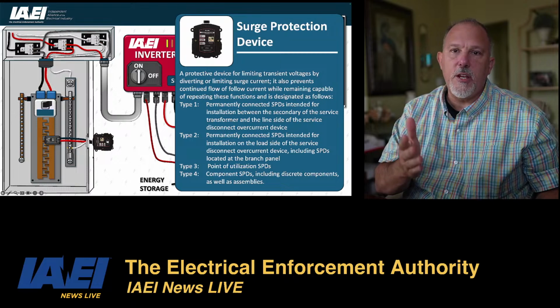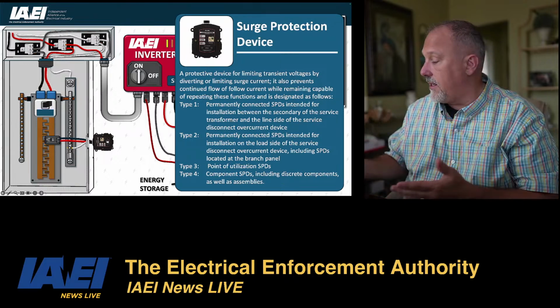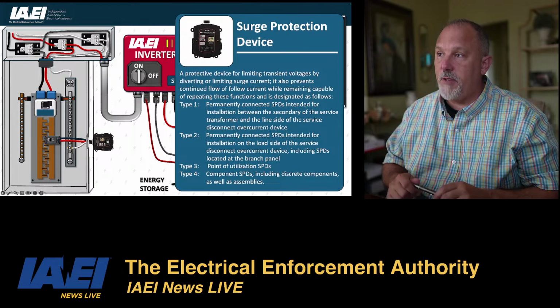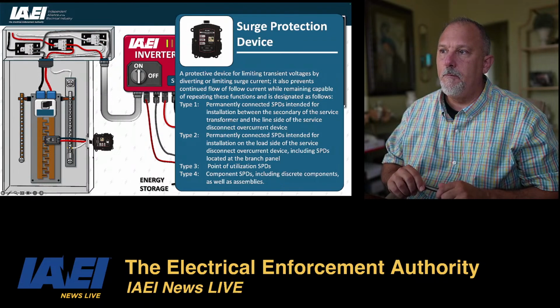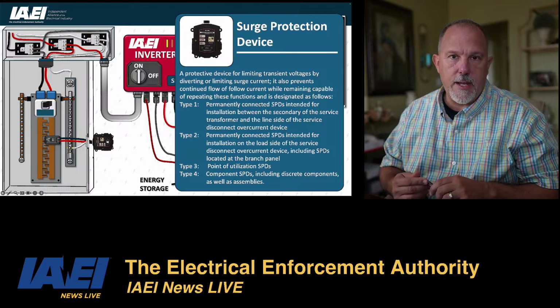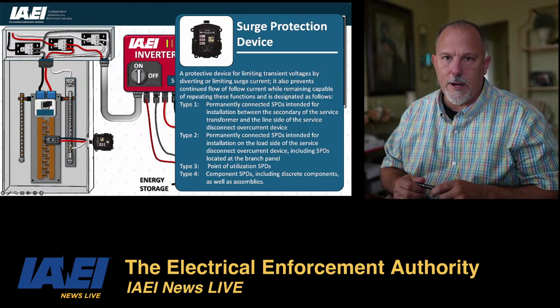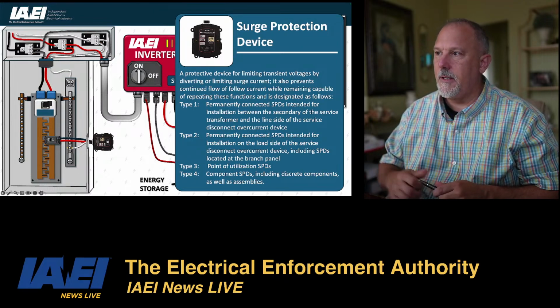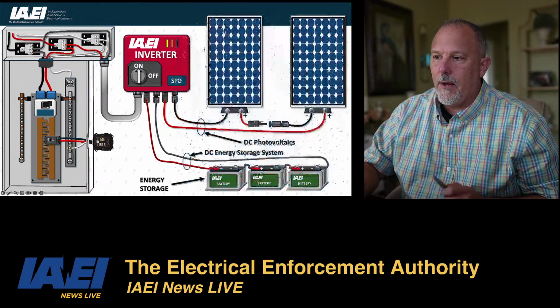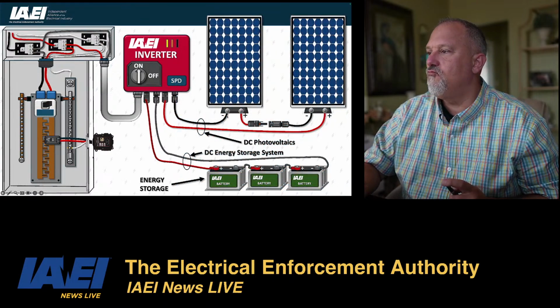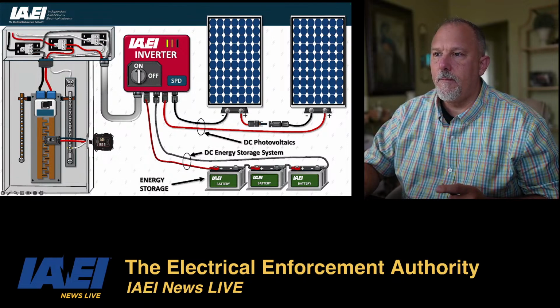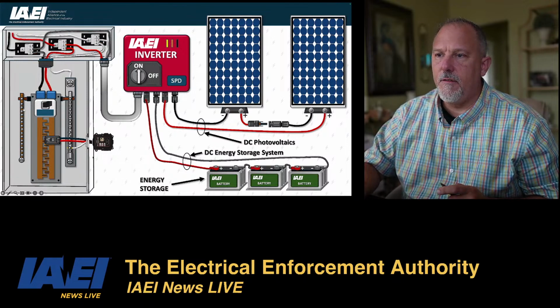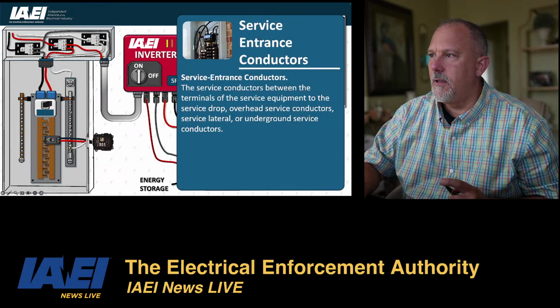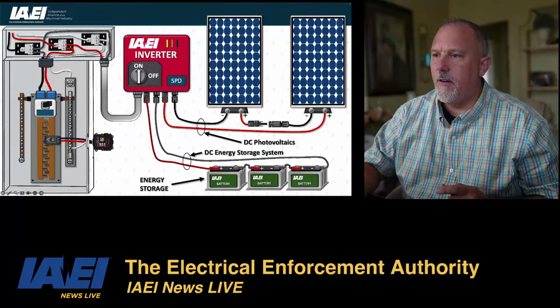You have to make sure that it doesn't count as one of the 6, which it doesn't. I believe we have permissions in Article 230 that the photovoltaic does not count as one of the required 6 disconnects. What else? I think that covers a lot of what's here.